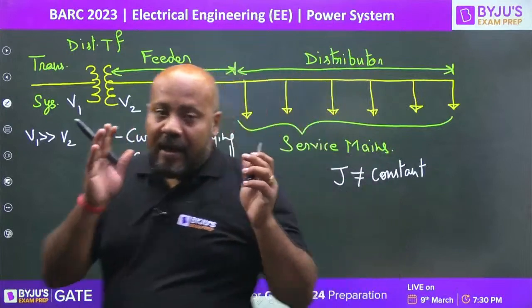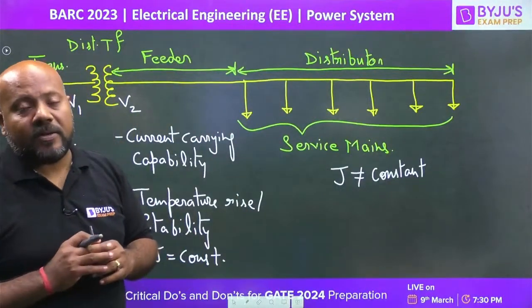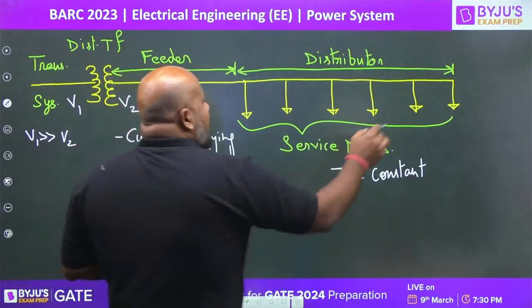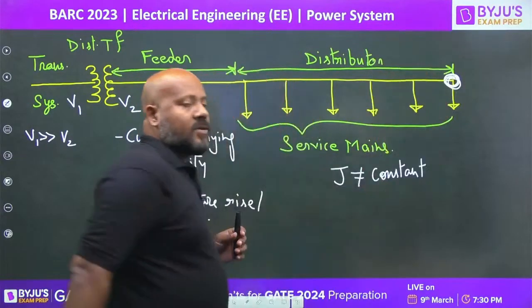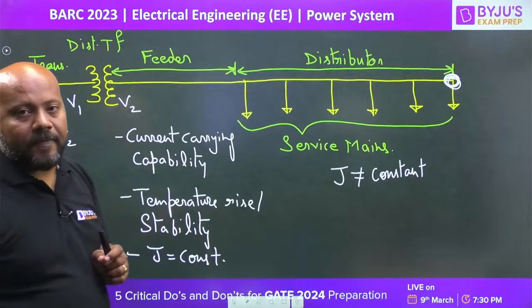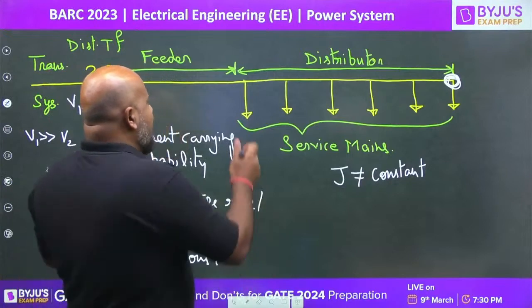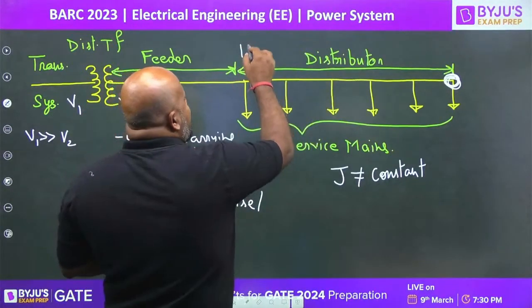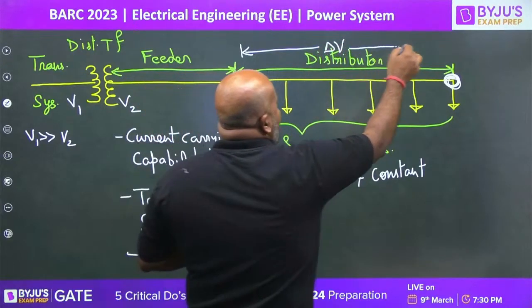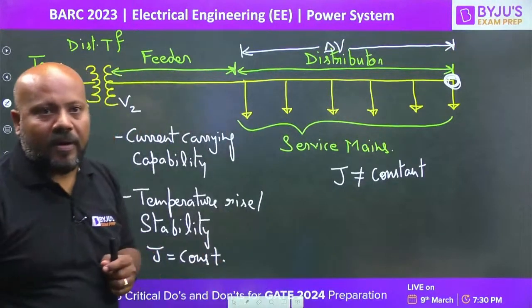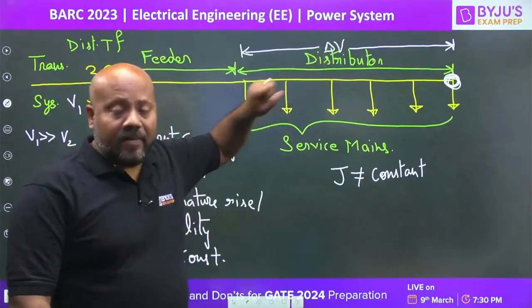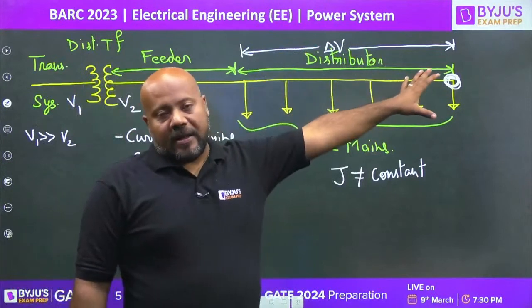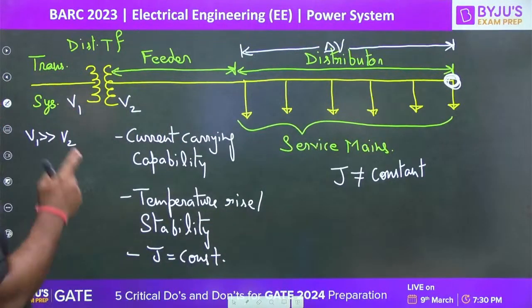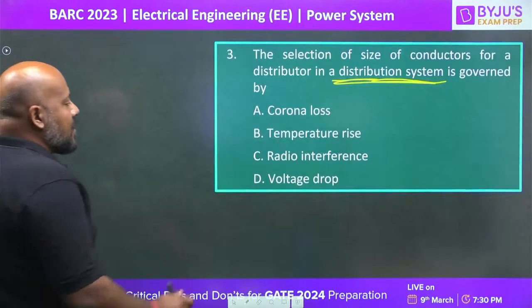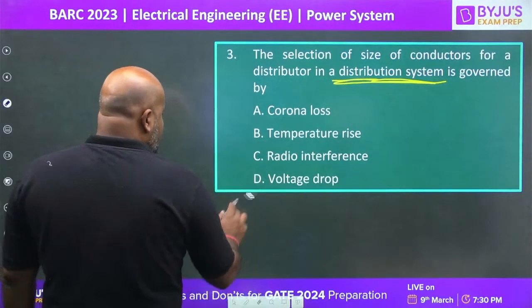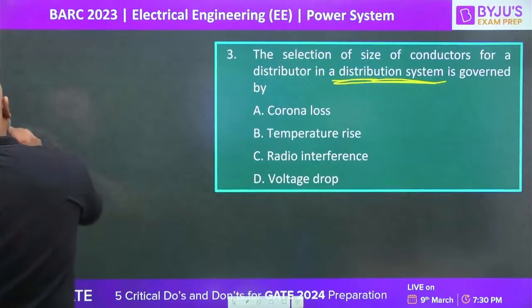It means as an honest power system engineer, what is your responsibility? Your responsibility is that you should ensure the quality of power supplied to the last consumer connected to your distribution system. How it is going to be ensured? If you go from the distributor starting to the end, there will be a certain voltage drop. Now, this voltage drop has to be within limits so that the power quality is not marginalized. And that is the reason while designing the distributor, one important criteria is voltage drop.